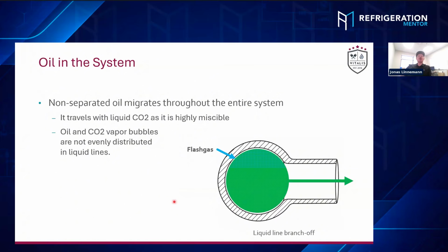By looking at the oil, it's generally evenly distributed here, but sometimes you see a higher saturation of oil at the bottom. So that's also why, in my opinion, it's much better to connect the liquid branch offs from the side, because otherwise you would get a lot of oil and liquid to the first evaporator, and the last evaporator is getting pretty dry and just flash gas. So that's generally a good way to distribute the right amount of liquid and oil and flash gas to the evaporators and the EVs.